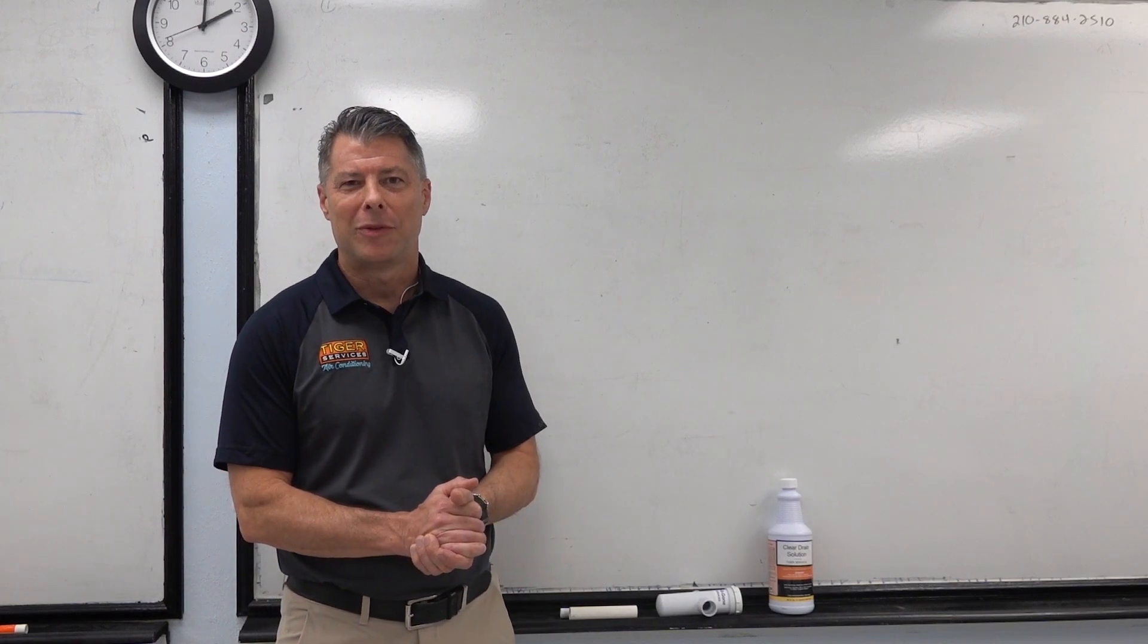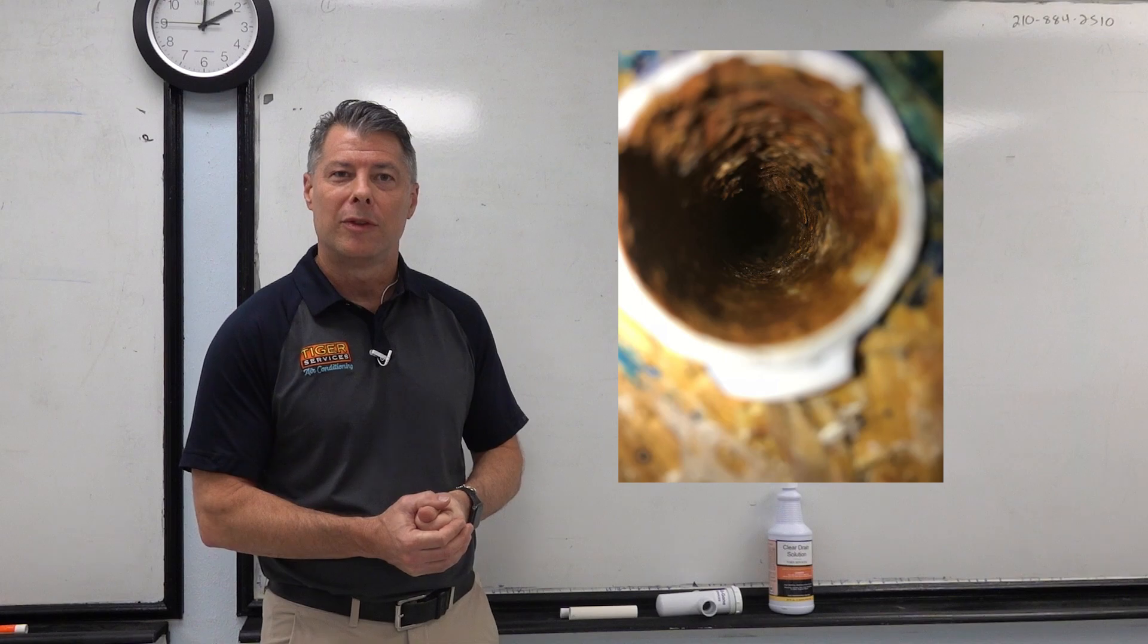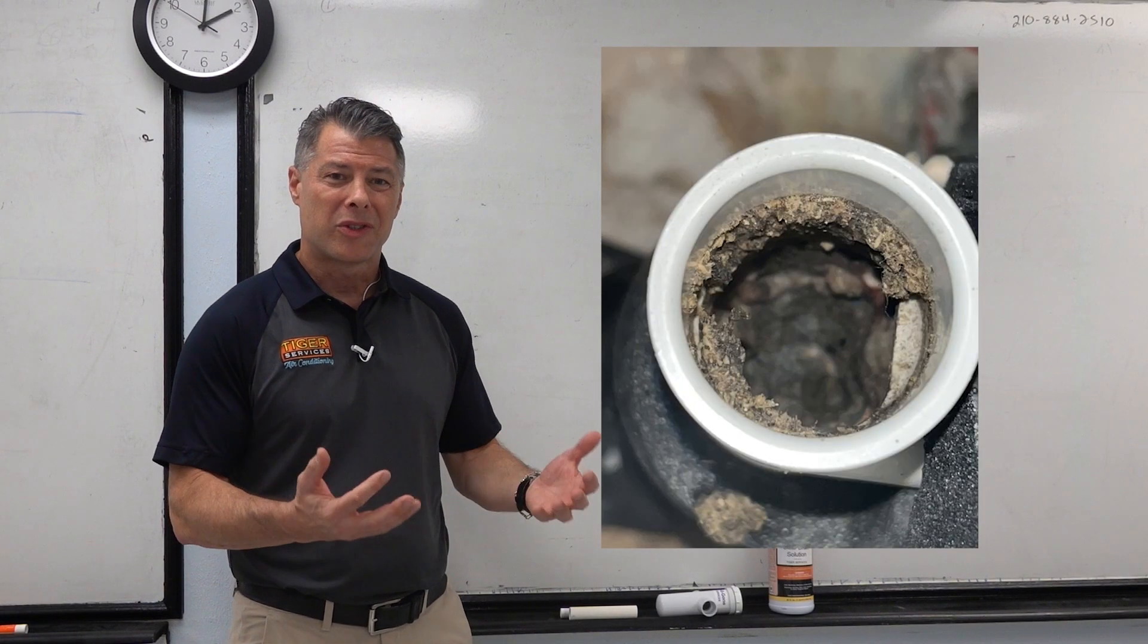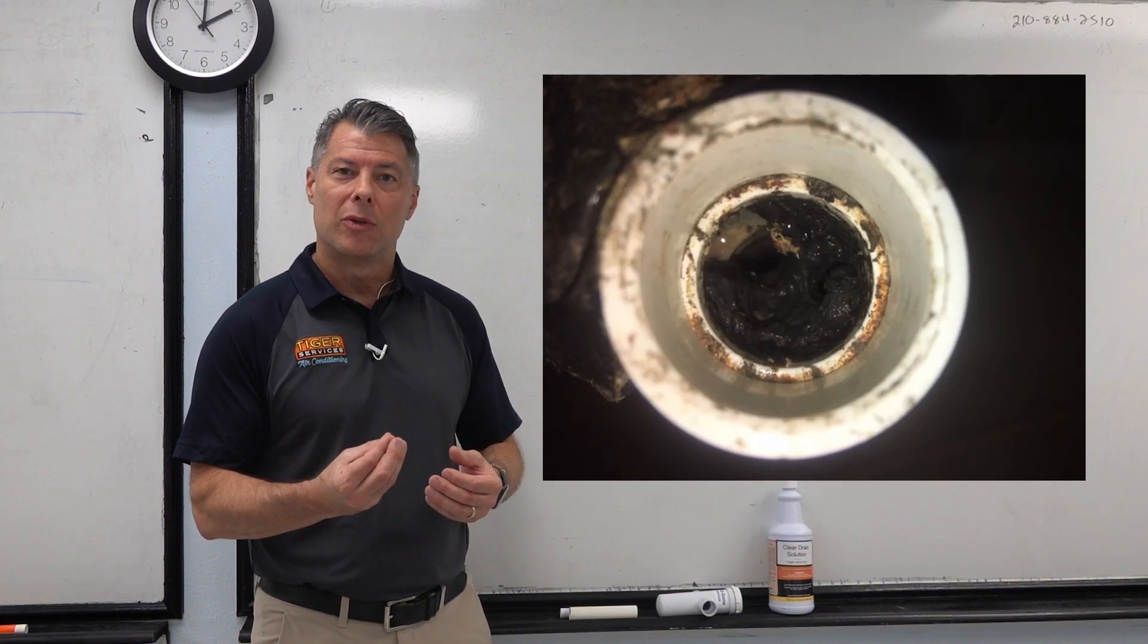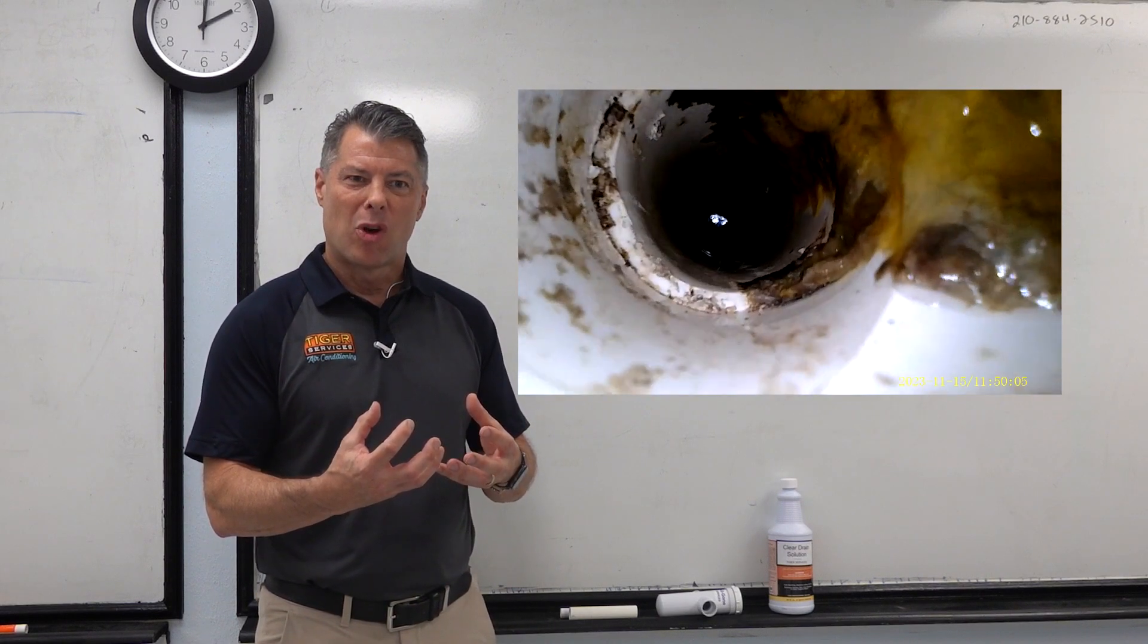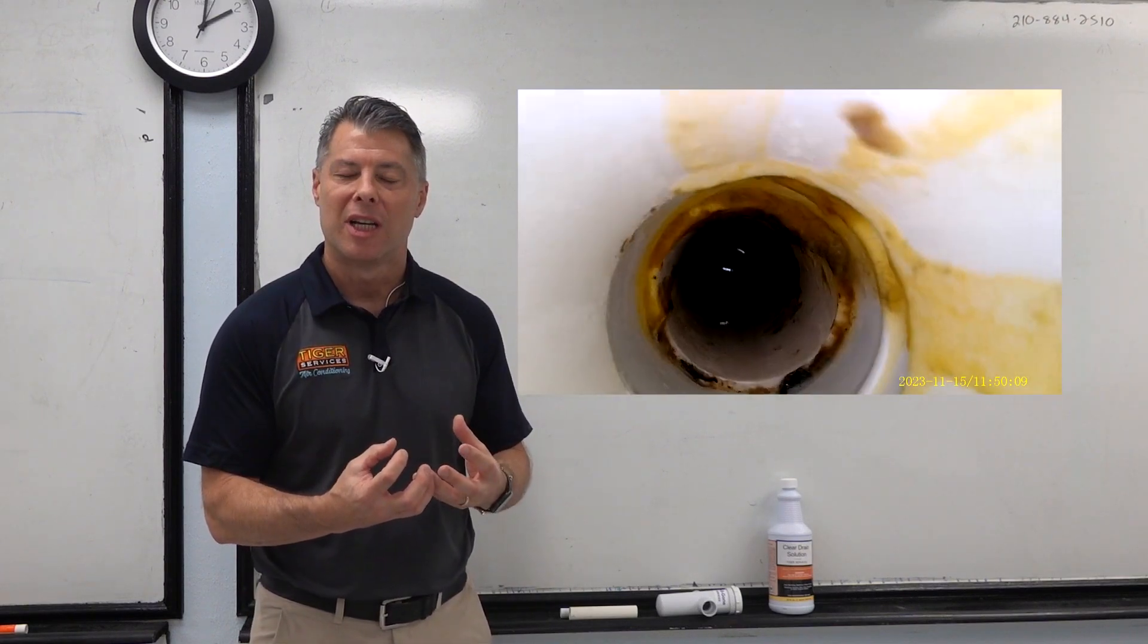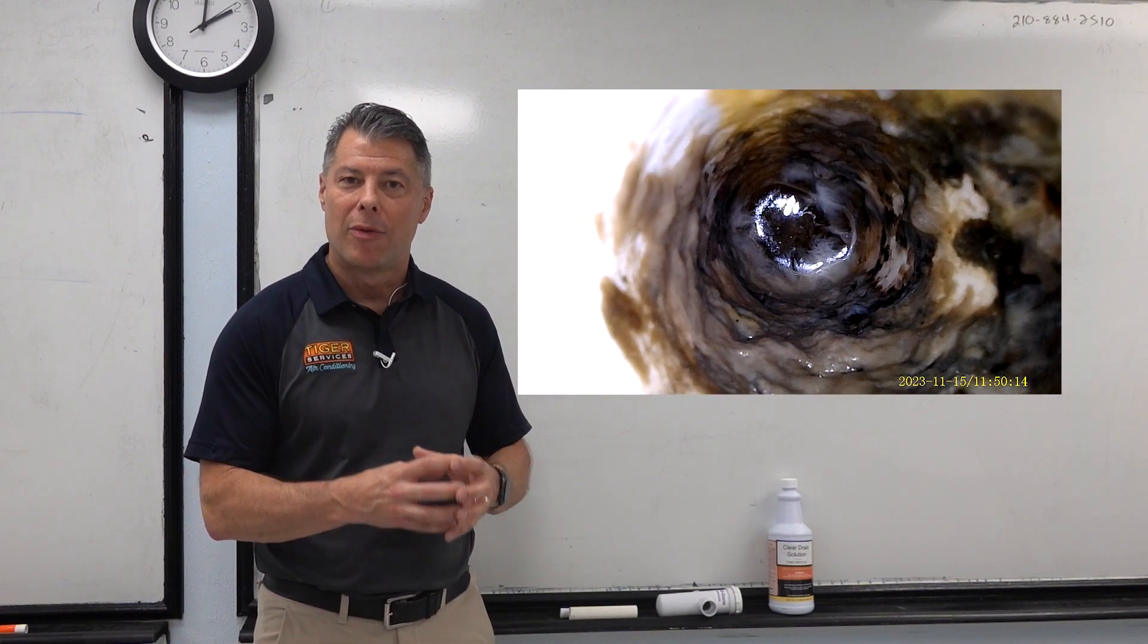So here are some examples of pictures that are from my techs out in the field when they're at a service call and maintenance call. What you're seeing is water will produce algae. So you're seeing algae buildup, slime buildup. There's almost like a quicksand texture to it, and it gets really hard when there's not water there.